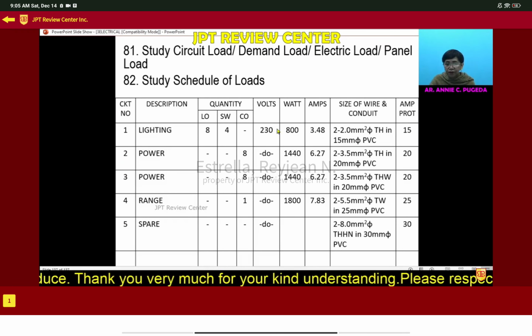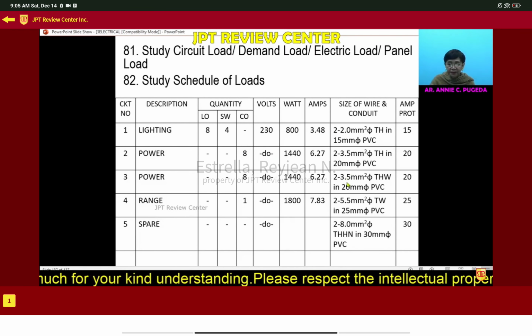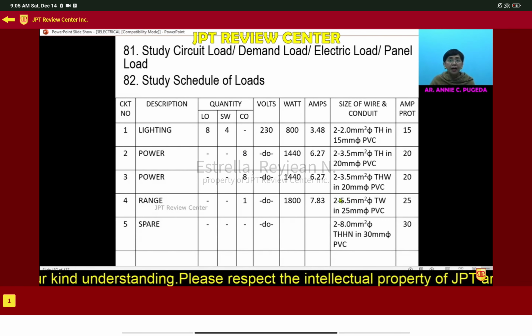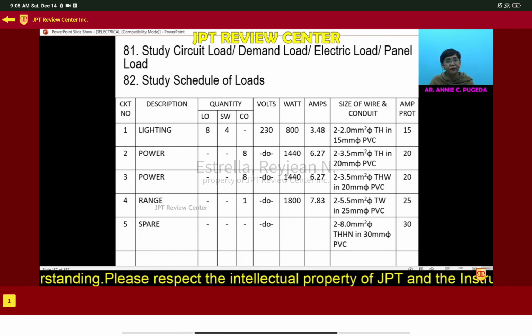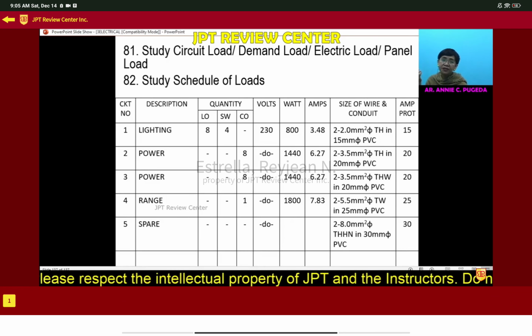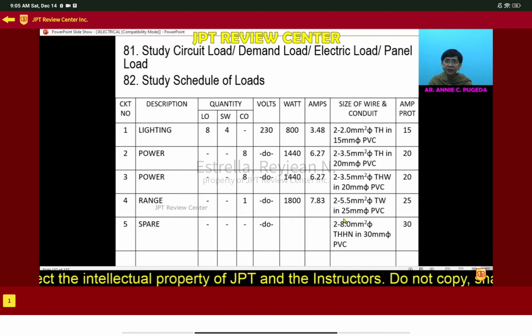So for every lighting of 8, the prescribed is 2.0. For every convenience outlet at 8, 3.5. For every independent circuit, talagang 5.5 na — standard is 5.0 but nominal is 5.5, wala kang mabibiling 5.0, laging 5.5. And if you have the spare, automatic na 8.0. Wala kang ginawang computation, just follow through the law.